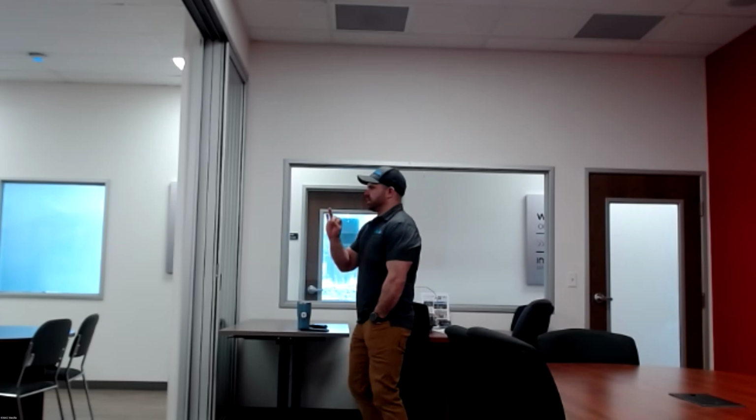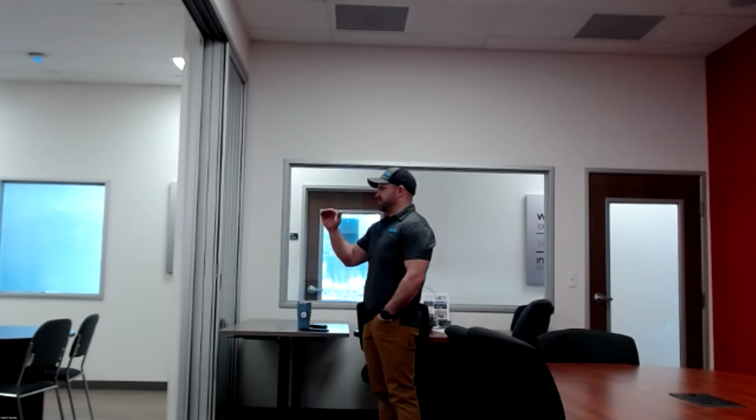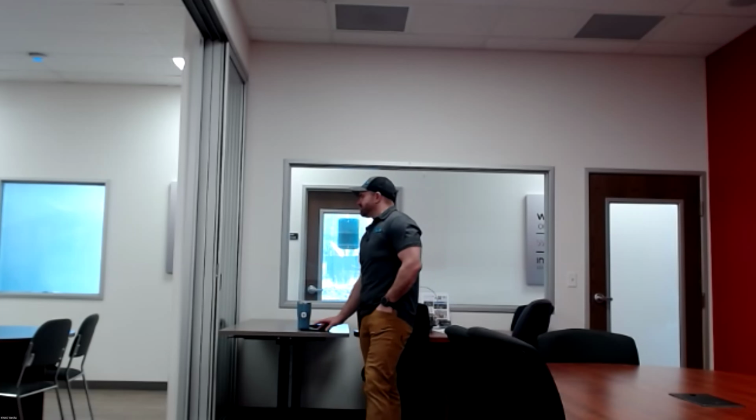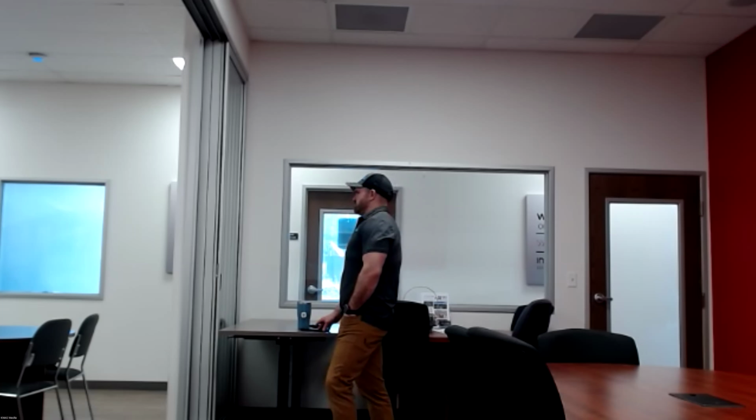Yeah, I've got a situation right now with two of the bedrooms' egress. Fire code does not grandfather well. There are some things that do, but smoke alarms and CO detectors, there's no grandfathering with that. There are some grandfather clauses, from 1979 and older, with things like sill height on windows, where it can be 48 inches, not 44 inches. But the window sizing, to the best of my knowledge, and the hardware, there are no grandfather clauses on that kind of stuff. So, this surge protector is installed in the electrical panel? Yes. Yeah.